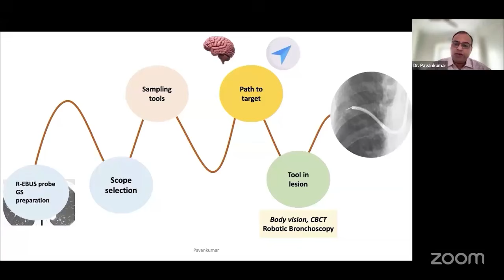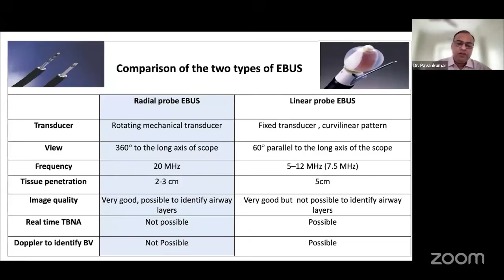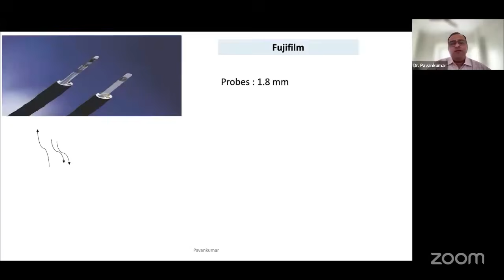So what is radial EBUS? It's a rotating mechanical transducer that rotates 360 degrees along the long axis of the scope, rather than the fixed transducer of a linear probe. It utilizes frequency up to 20 megahertz with good tissue penetration up to 3 centimeters and excellent imaging of the peribronchial layers. But it lacks real-time TBNA. What is possible in linear EBUS, real-time biopsies, is not possible in radial EBUS. You have to take out your radial probe and put your accessories through the working channel. And it doesn't give you a Doppler signal to identify blood vessels, which is possible with your linear probes.